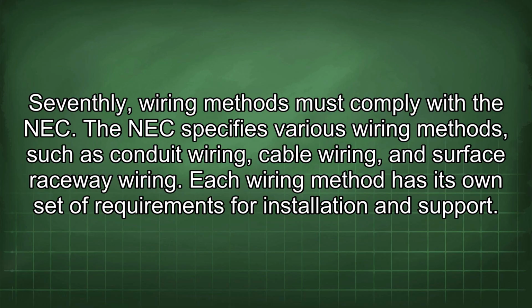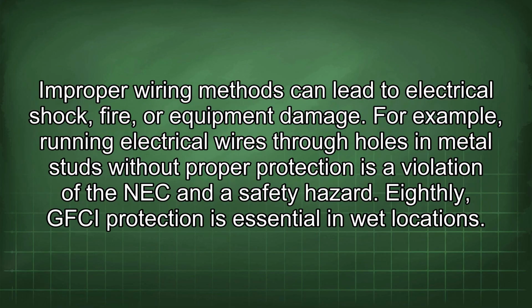Seventhly, wiring methods must comply with the NEC. The NEC specifies various wiring methods such as conduit wiring, cable wiring, and surface raceway wiring. Each wiring method has its own set of requirements for installation and support. Improper wiring methods can lead to electrical shock, fire, or equipment damage. For example, running electrical wires through holes in metal studs without proper protection is a violation of the NEC and a safety hazard.